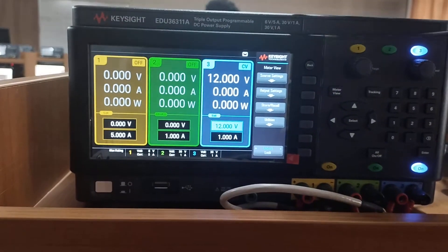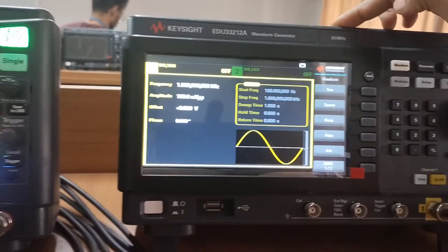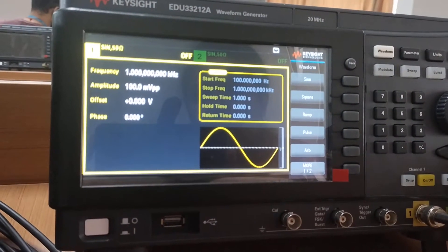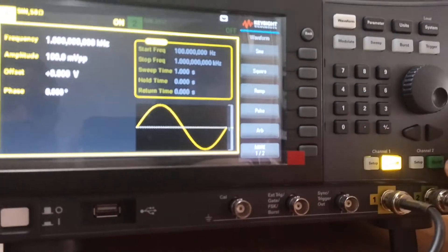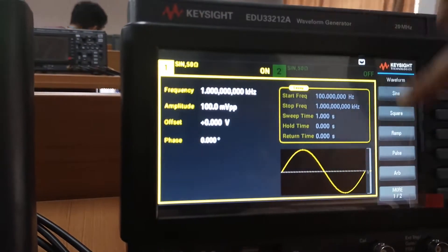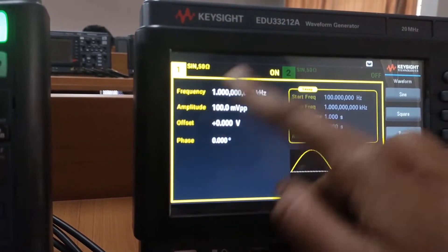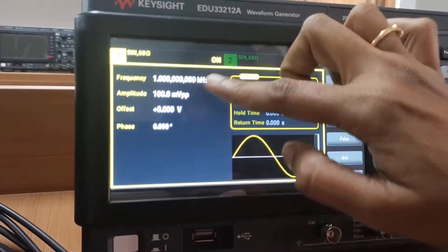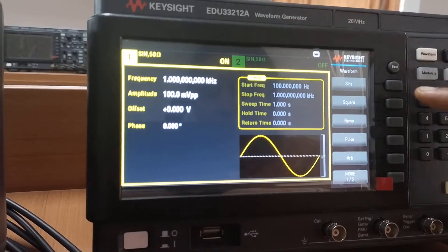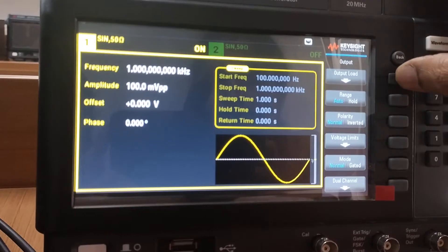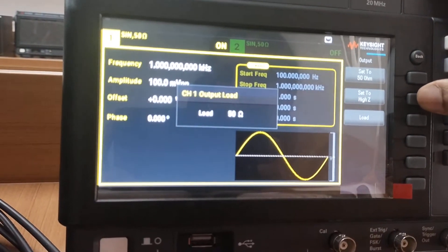Now moving to the Keysight waveform generator settings. We are going to use two channels — Channel 1 for the message waveform and Channel 2 for the carrier waveform. Channel 1 is highlighted in yellow. Before setting frequency and amplitude, we first configure the output load impedance to high impedance.